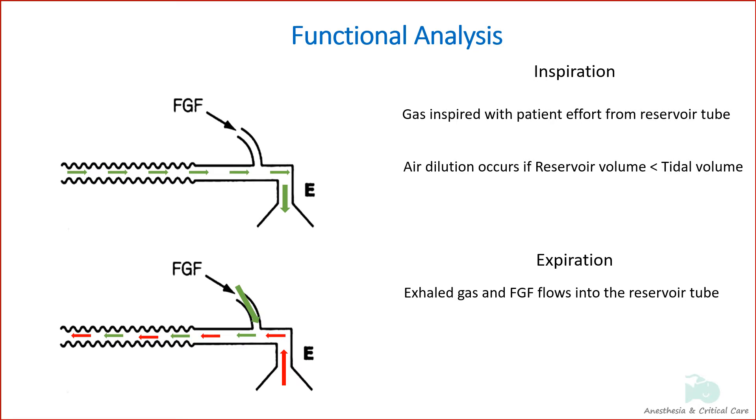During end-expiratory pause, fresh gas continues to fill the reservoir tube and flushes out exhaled gases. The fresh gas collected in the reservoir limb is then inspired on the next inspiration.